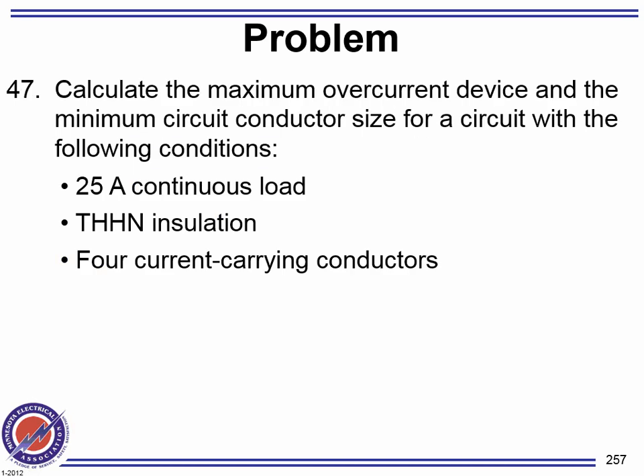Okay, now we have a continuous load, and we have a derating because of current carrying conductors. If you have two things at the same time, what did we say we do? We treat them separately, find the continuous load, size them separately, and choose the largest of the two. Am I making sense? So let's go size the load.